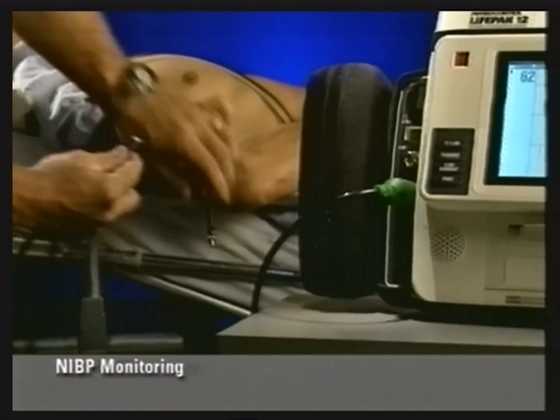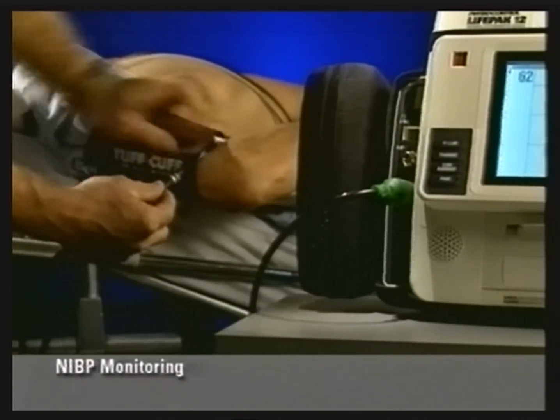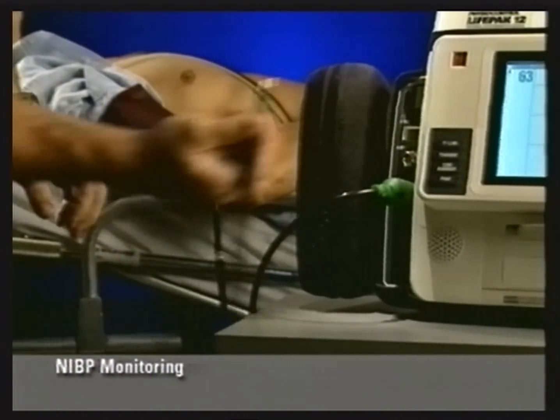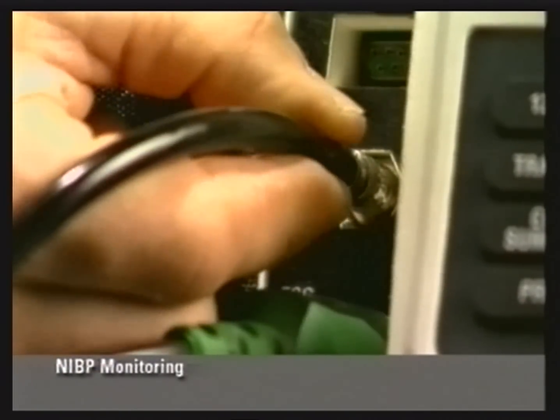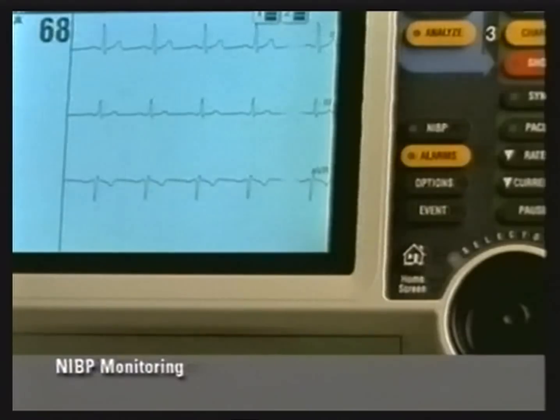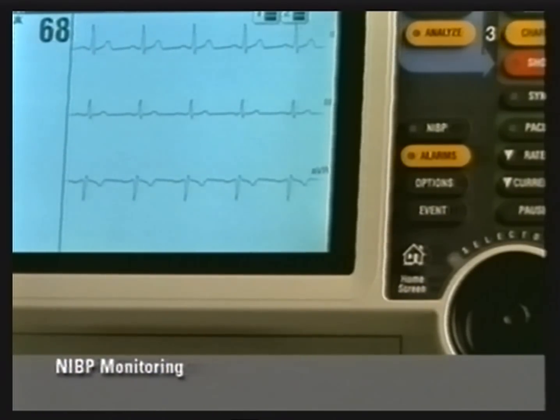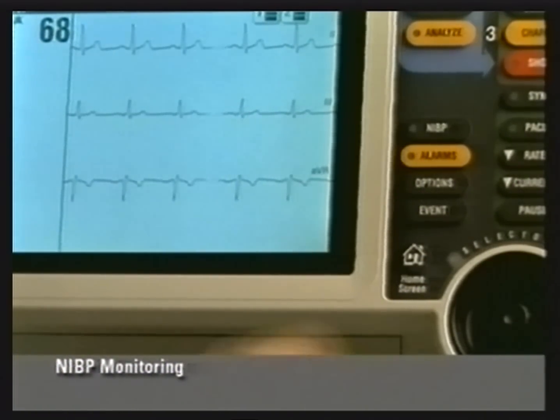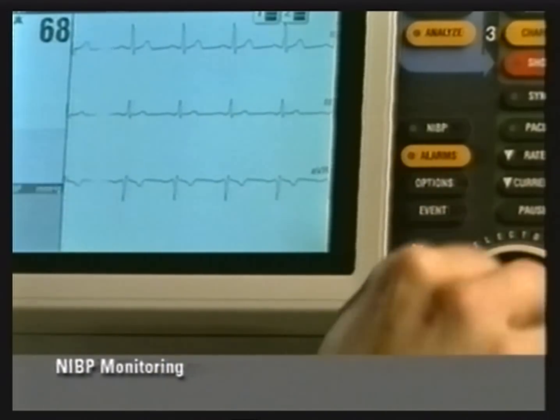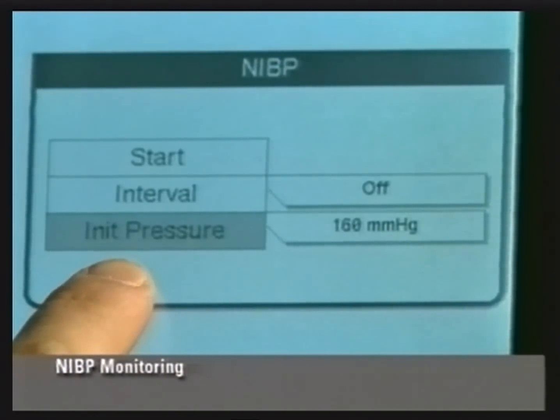Connect the tubing to the cuff and connect to the NIBP tubing connector on the monitor by pushing the connector straight in until a snap is heard. Before taking the first blood pressure measurement, change the initial cuff inflation pressure if necessary. The initial cuff inflation pressure should be set to 30 millimeters of mercury higher than the patient's systolic pressure. The factory default for the initial inflation pressure is 160 millimeters of mercury. After a first reading, the NIBP monitor automatically adjusts the inflation pressure to be about 30 millimeters of mercury higher than the patient's systolic pressure.